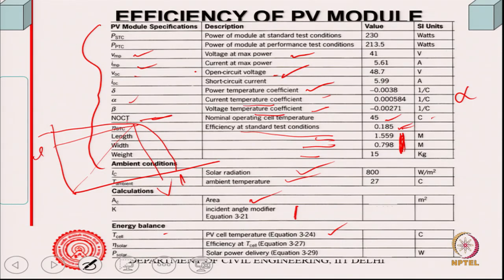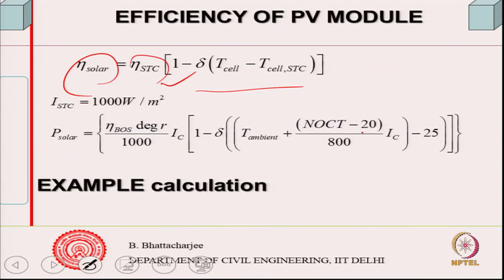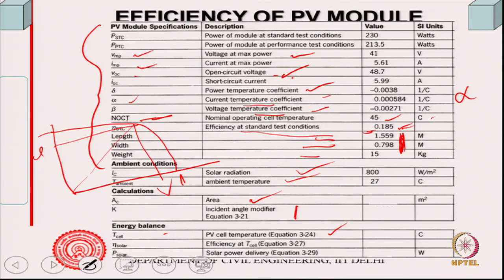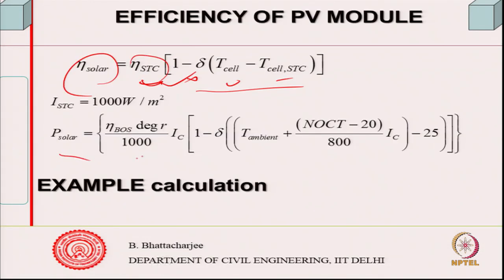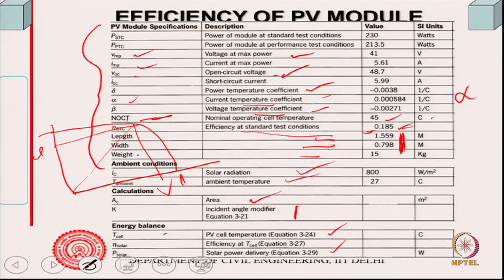Efficiency can be calculated from the formula since efficiency at standard condition is already given as 0.185. Delta is known, T_cell has been found, and T_cell under standard condition is also given. So solar power P can be calculated based on this formula — for example, for 1000 W/m² standard condition. That is how one can calculate the power output.